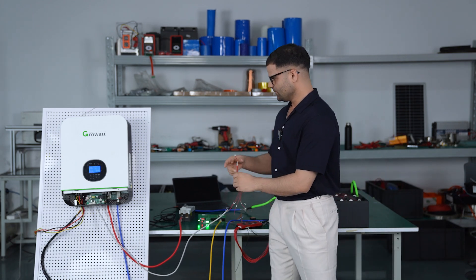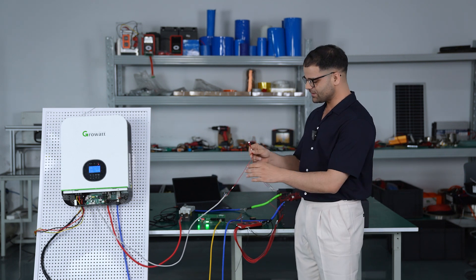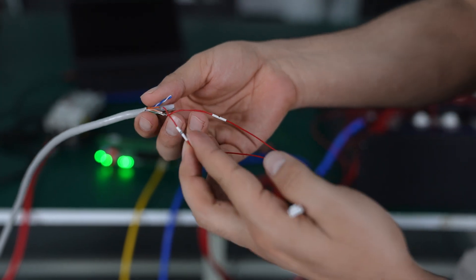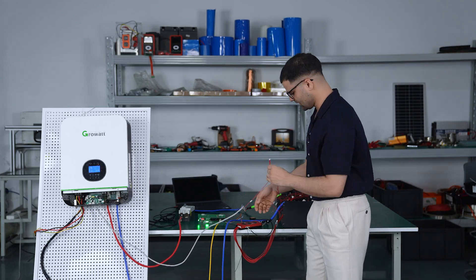Today we are connecting the inverter to the BMS directly through an RS485 cable. You need to make sure you are connecting the RS485 A and B cables correctly to the BMS. We have connected it correctly, so now we will connect it to the BMS.